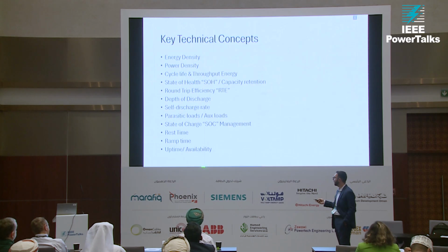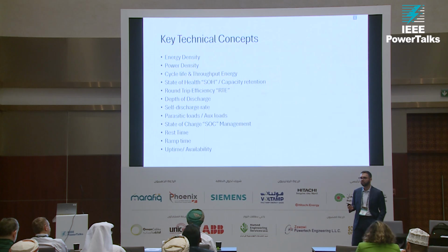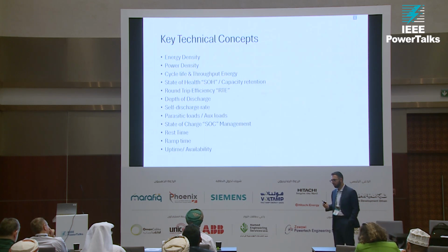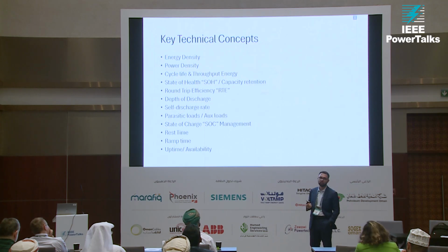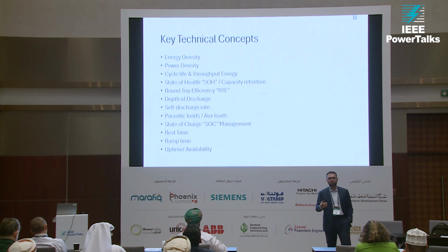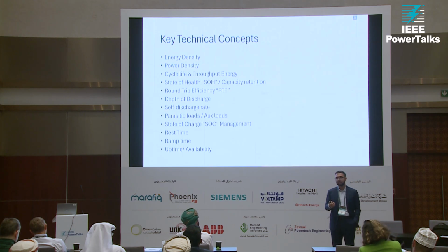The nice thing about electrochemical batteries, as shown in the industry over the past 10, 12 years we've been running these in the US, is that you can get up to 98% availability in your battery system, which is quite impressive. At Calpine, we operate a large fleet of gas-fired generation and a large fleet of batteries, and we're considered one of the most reliable, high availability generation companies in the industry. Our gas fleet barely hits 90% availability. Our battery fleet hit 99.2% availability, which is quite impressive.